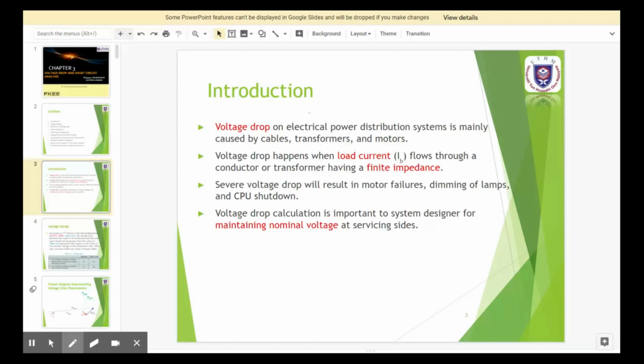So severe voltage drop will result in motor failures, dimming of lamps, and CPU shutdown. It can cause failures if we have severe voltage drop. Therefore, voltage drop is very important to be calculated so that the system designer can maintain the nominal voltage at the servicing sites.